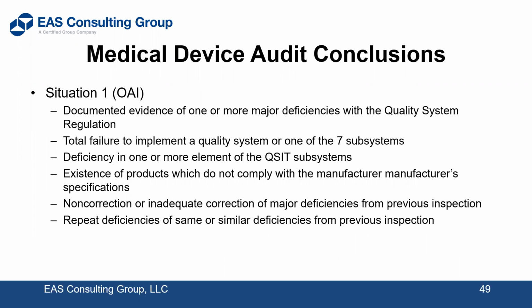What that means is you have a major problem here in one of these areas, or maybe all of the areas. I've seen some firms that have nothing, no procedures, no forms, nothing. They just make a product and out it goes. And so that basically means that you don't have a quality system at all. You can have major elements of these systems, say for design controls, that you do not do design verification or design validation, which is a major area in design control. So if you don't do that, then that's a problem with design controls.